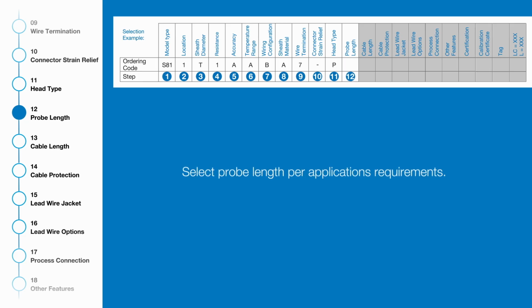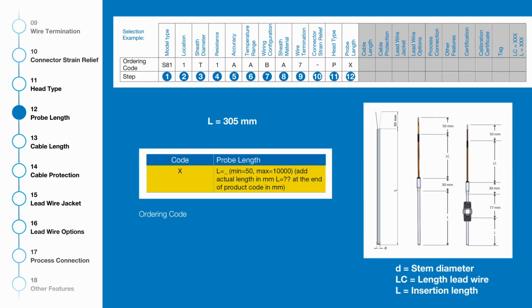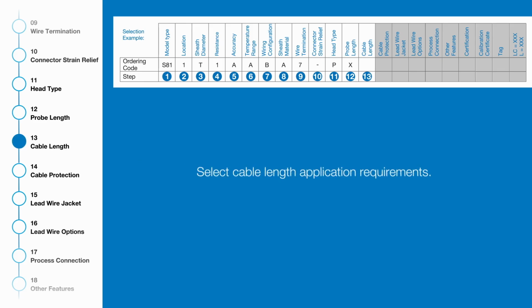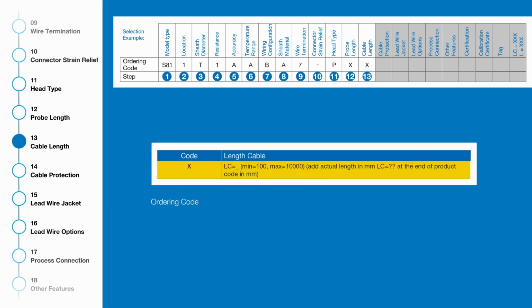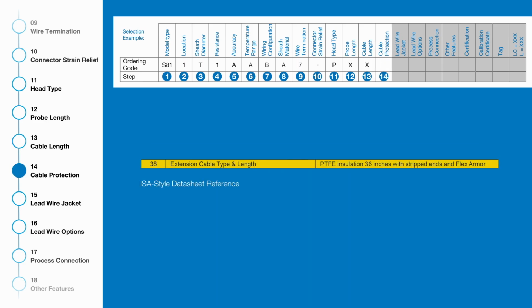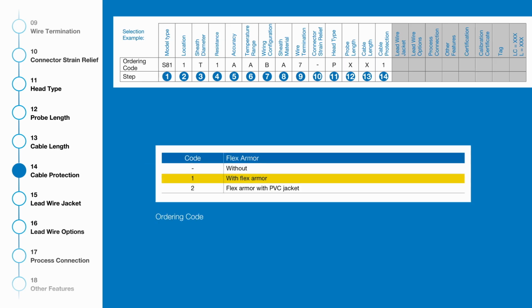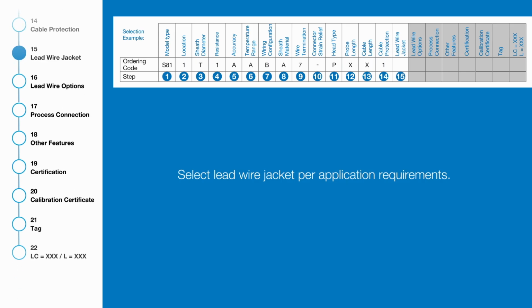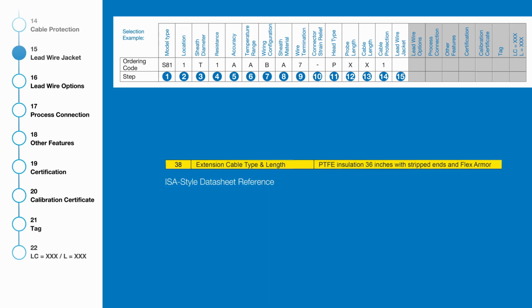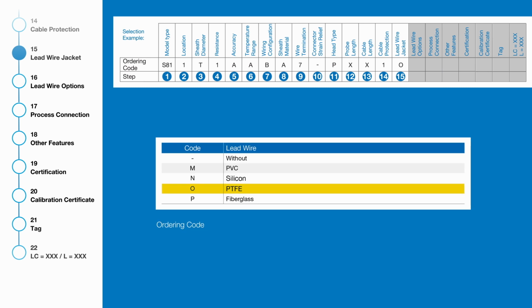This section is for probe length. In the code, we're going to put X, and the length, L equals 305 millimeters, will be put at the end of the code. For the cable length, we're also going to put an X in the code, and we're going to put the LC equal to 915 millimeters at the end of the code. For cable protection, there was an option here for flex armor, so we're going to select code 1 with flex armor. The requirement for the lead wire jacket was PTFE, so we're going to select the letter O.